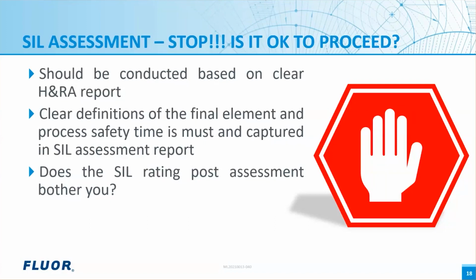So in the example Veronica mentioned, for tank level, once high level is attained, if filling continues, after how much time will the tank see spillage? If that is 5 minutes, then all the actions of closing the inlet valve and stopping the pumps should practically happen within 2.5 minutes.